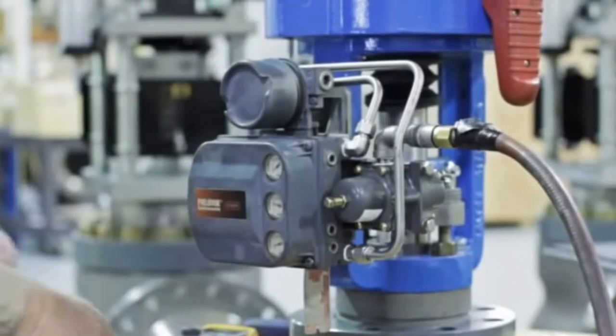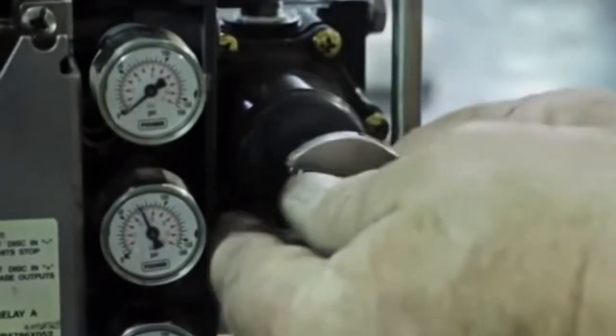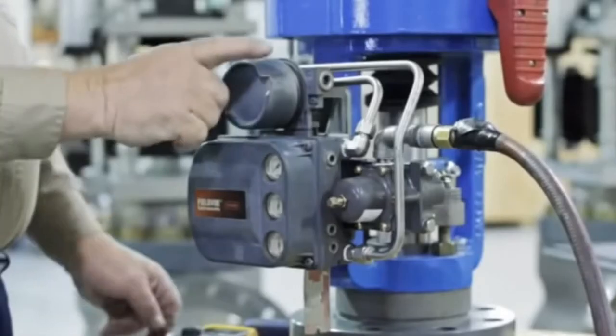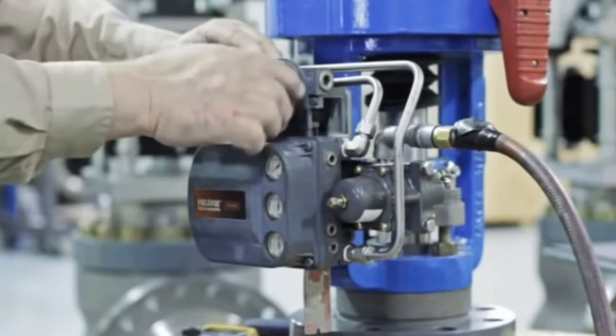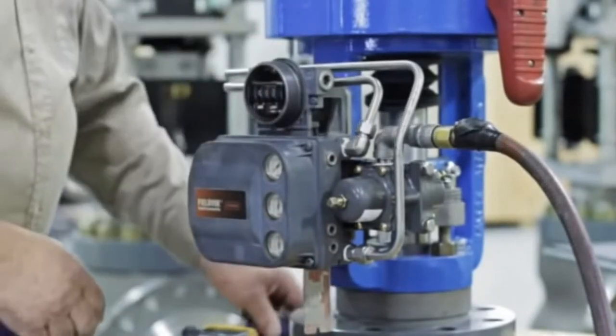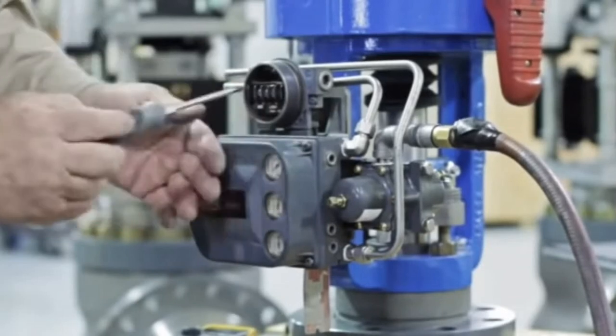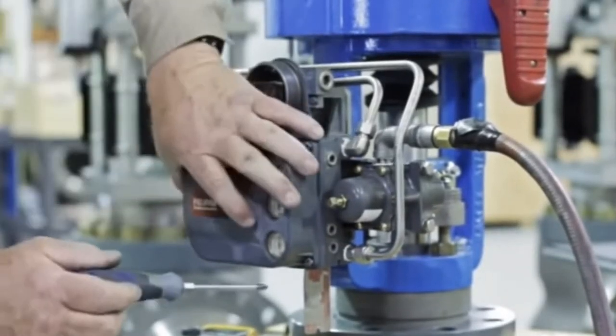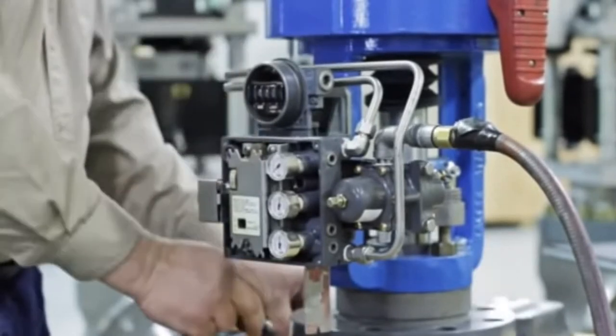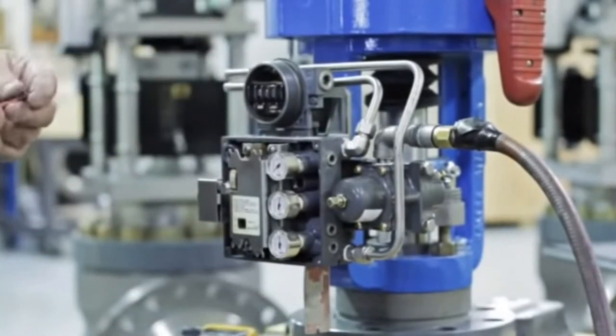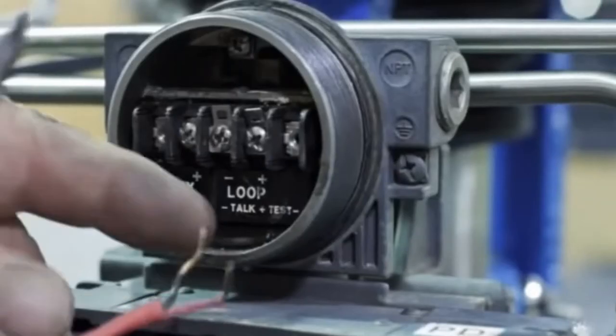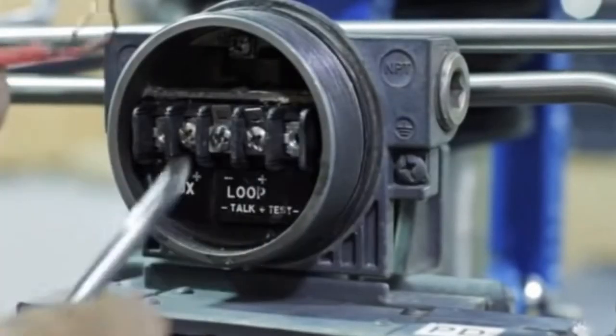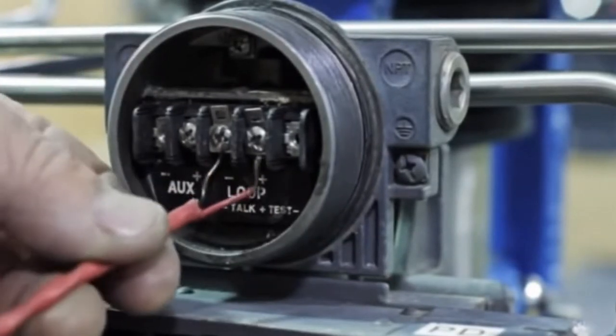Connect the air supply. Check the air supply gauge and adjust the supply regulator until the desired pressure is met. Note that the maximum air supply pressure is 150 psi. Remove the covers. Connect the power supply current source to the terminal box loop terminals. Red goes to positive and black negative.